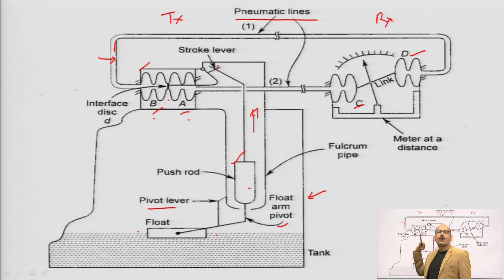When the level of the water increases or decreases, this push rod will also make some displacement. That displacement goes toward these bellows through this stroke lever, which will expand or contract bellows A and B. Because of the change in the position of the push rod through the stroke lever, you can see that this stroke lever is connected here to the interface disc. This interface disc is going to change the bellows condition, whether it is going to expand or contract.